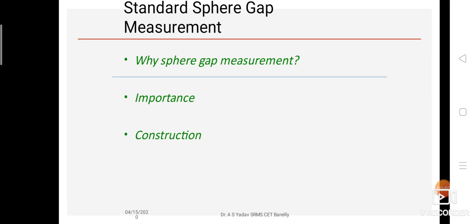Good morning, students. Today we are discussing the sphere gap method for the measurement of high voltage. In this method, we measure high AC, DC and impulse voltage under constant atmospheric conditions, at a spark over voltage of 30 kV at 1 centimeter spacing in air at 20 degrees Celsius temperature and 760 torr pressure. The spheres can be attached either vertically or horizontally.